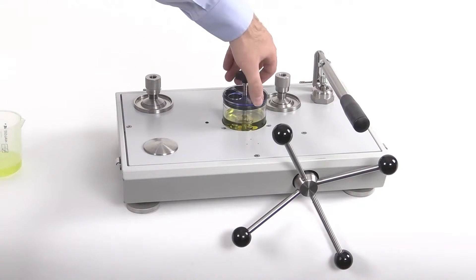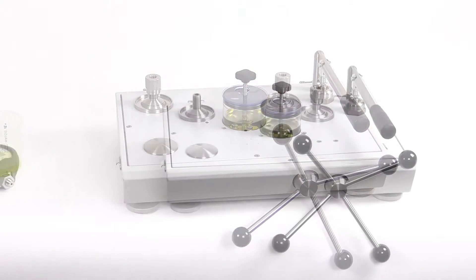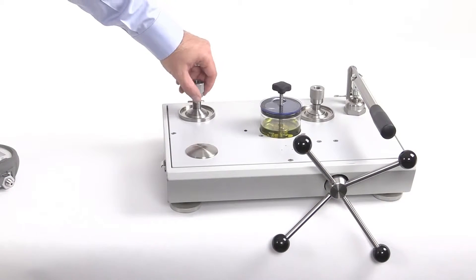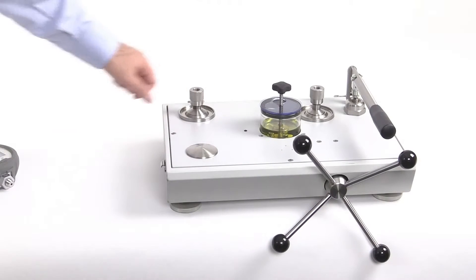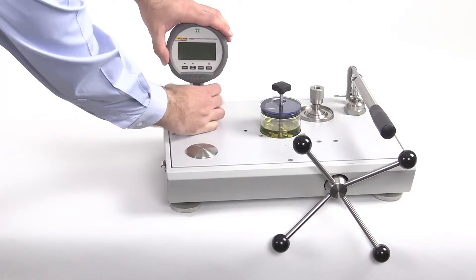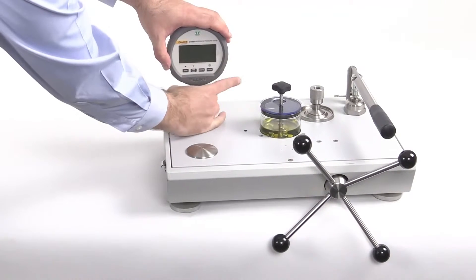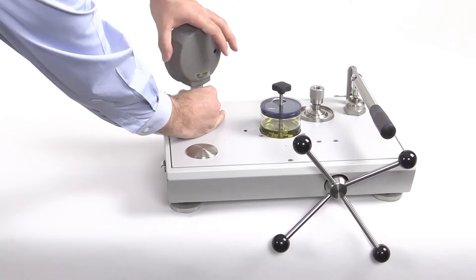Then rotate the dust cover back to cover the hole. The 2700G reference pressure gauge can be connected without the use of PTFE tape or tools. The hand-tight connection is made by screwing the quarter NPT adapter onto the test port. This is a left-handed thread. The reference gauge can then be attached to the adapter.